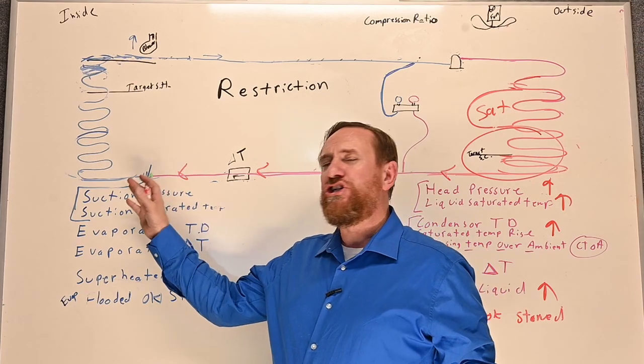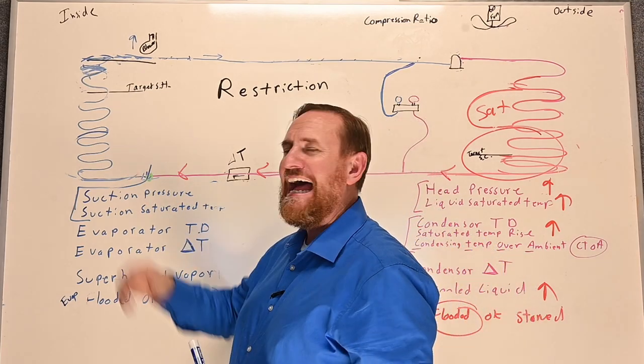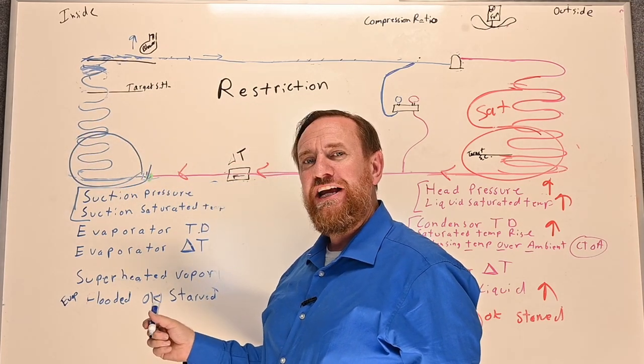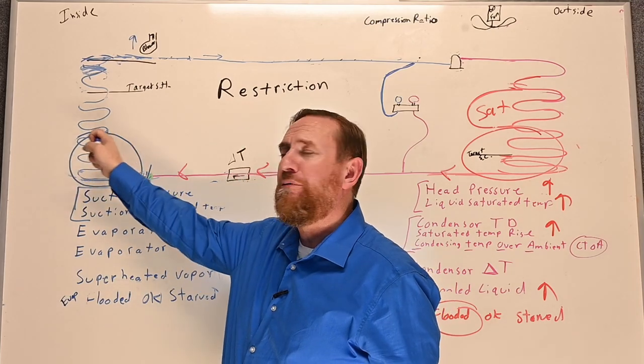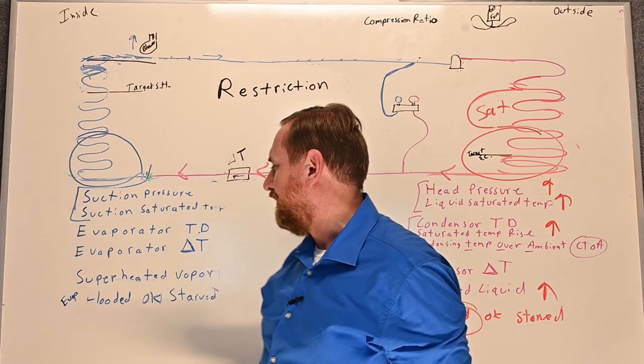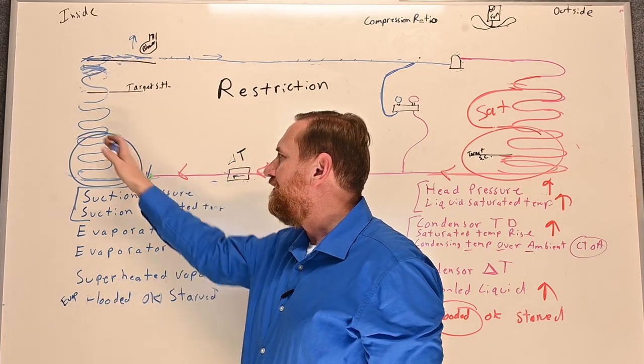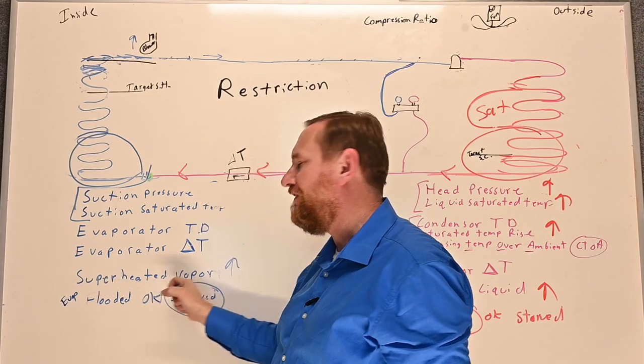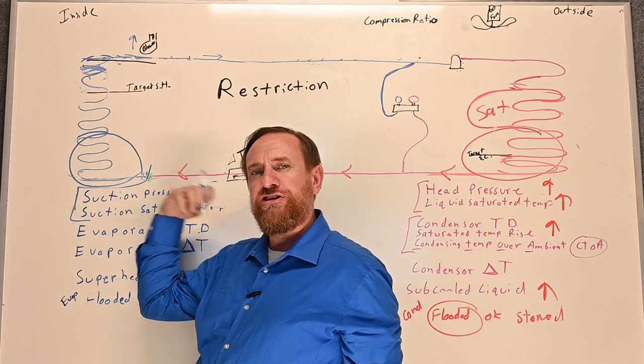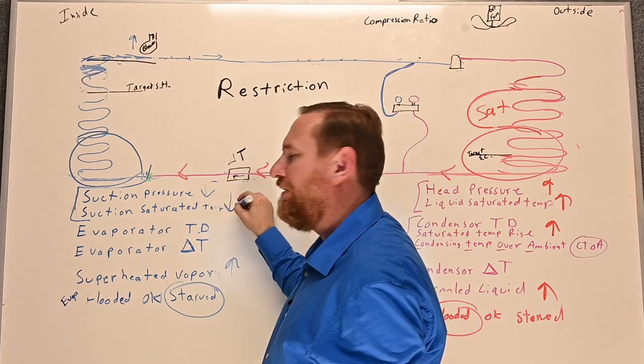On the evaporator side, because we're restricting refrigerant flow, it's not getting to the evaporator coil — we have the opposite effect. We don't have enough liquid refrigerant, so we end up with less saturation there. Less saturation means the refrigerant boils away very fast, so superheat goes up. Too much superheated vapor means not enough liquid saturation mixture — the evaporator coil is starved. Because there's less refrigerant in the evaporator coil, we end up with a lower suction pressure, which also means a lower saturated temperature.